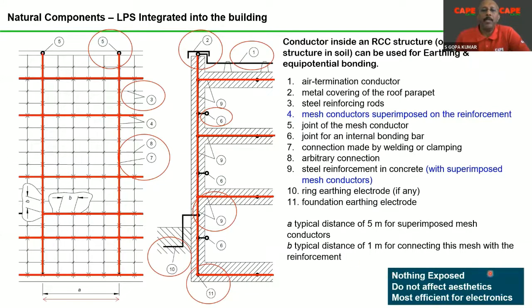In this particular case, the down conductors and the earth electrodes or the foundation earthing are not exposed. They do not affect the aesthetics of the building, and it is most efficient for electronics. Whenever there is a current flow through the structure, the current is split into several hundreds of routes. As a result, the concentration of current through any one conductor is less, because the current flows through the entire building. As a result, the effect of the current flow with a large di/dt, the rate of change of current, is reduced, and you get maximum protection for your electronics.